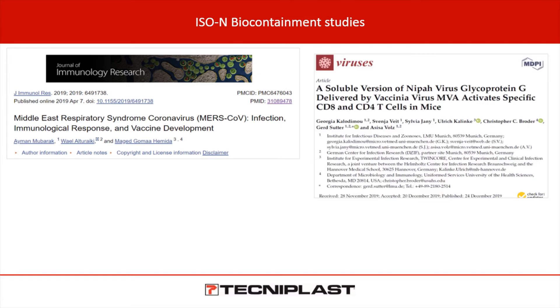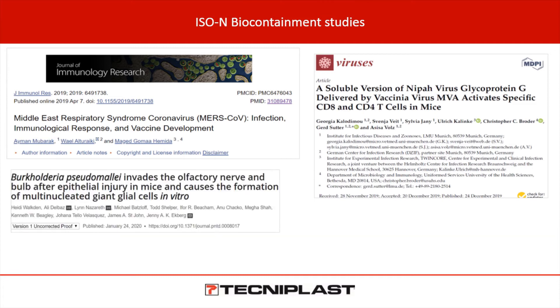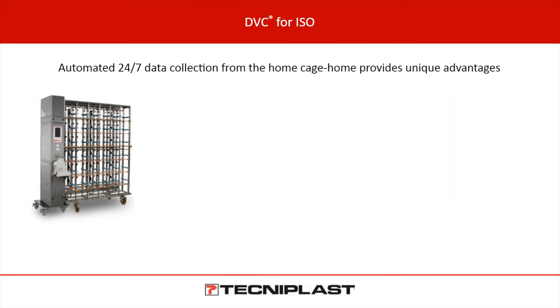The isopositive cage on the left is specifically for bioexclusion, where HEPA-filtered air from the rack passes through the HEPA filter on the cage unit itself via sealed spring-valve ports in the back of the cage — maintaining that seal anytime the cage is removed from the rack, providing double HEPA filtration. The isonegative cage on the biocontainment side allows HEPA-filtered air to enter passively, then pass through a HEPA filter before exiting the cage into the rack plenum, which is also HEPA filtered before exiting the rack — double HEPA filter exit on the biocontainment side. ISO-negative biocontainment studies include MERS/COVID infection for vaccine development, NIPAH virus, BSL-3 bacterial agent Burkholderia pseudomallei, and Zika virus.